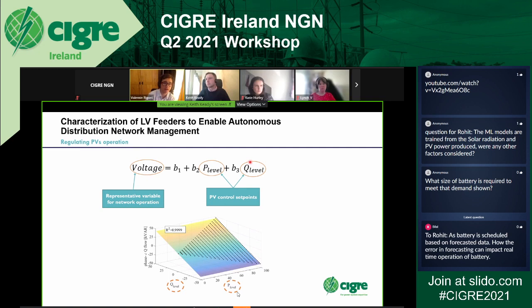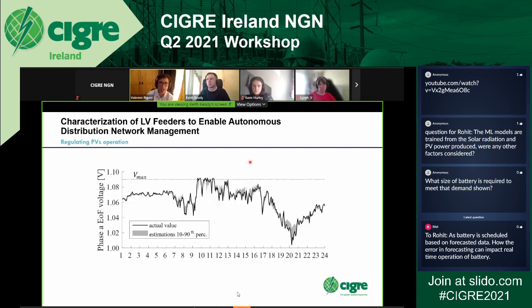So then you can modify either active or reactive power from the PV according to whatever the characteristics of the inverter are, and then bring that voltage back to safe operation. And at the same time, you could also minimize losses on the system or minimize currents or minimize the reactive power flow exchange with the upstream network, curtailment, whatever you want, because all those variables, you can characterize them with these surfaces. And at the end of the day, you get an operation of the grid where your voltages, following some objective function, are maintained within the limits that are defined by the grid code.